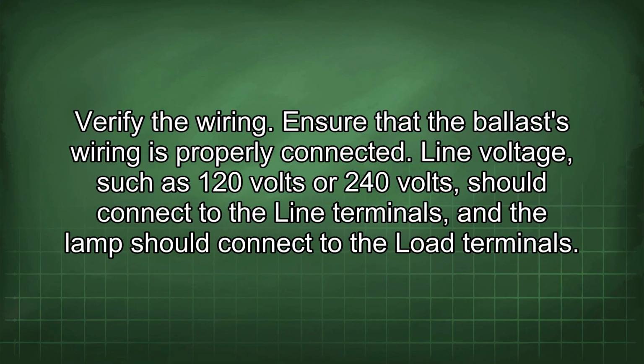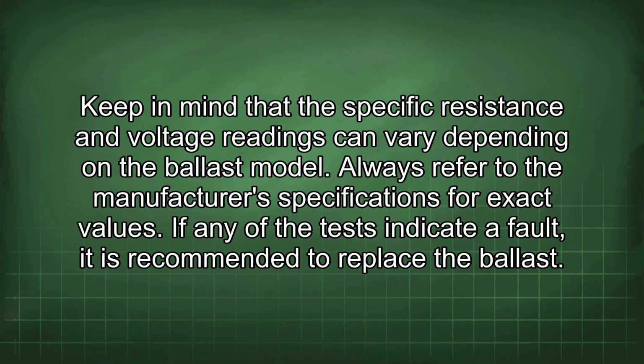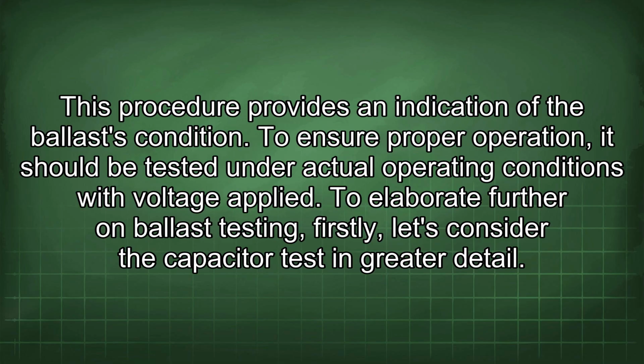Verify the wiring. Ensure that the ballast wiring is properly connected. Line voltage, such as 120 volts or 240 volts, should connect to the line terminals, and the lamp should connect to the load terminals. Keep in mind that the specific resistance and voltage readings can vary depending on the ballast model. Always refer to the manufacturer's specifications for exact values. If any of the tests indicate a fault, it is recommended to replace the ballast. This procedure provides an indication of the ballast condition. To ensure proper operation, it should be tested under actual operating conditions with voltage applied.